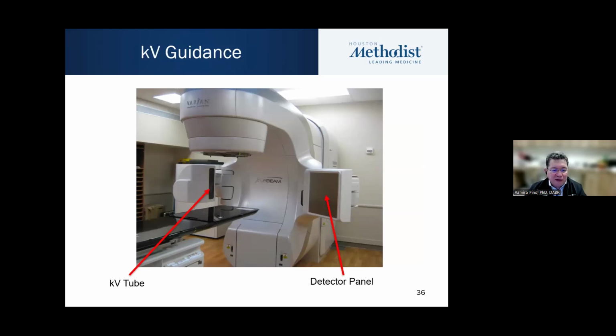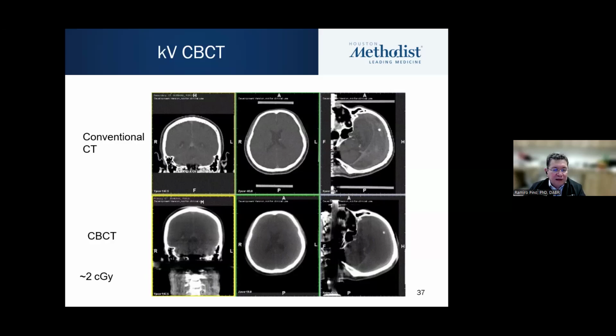For instance, for this particular machine, which is a Varian TrueBeam, you have here a mounted onboard imager that has a tube and an X-ray detector, a panel, and you can acquire either planar images or cone beam CT. And this is an example of a comparison between a conventional CT and a cone beam CT. And generally, cone beam CT tends to have lower image quality, although there have been significant improvements in that regard lately.